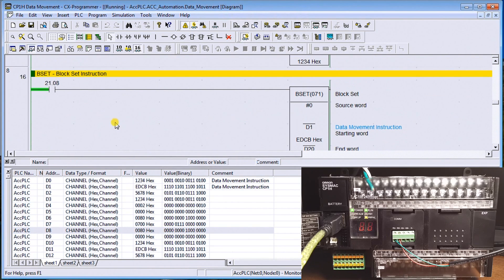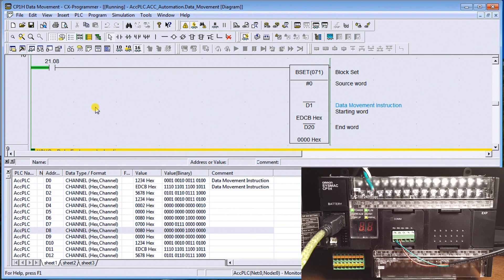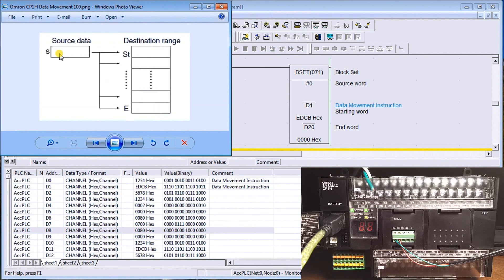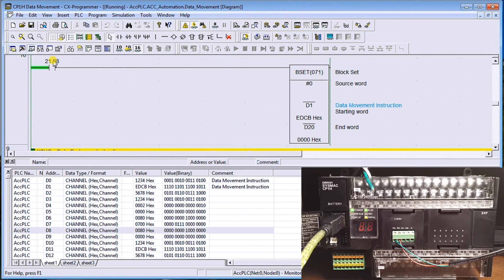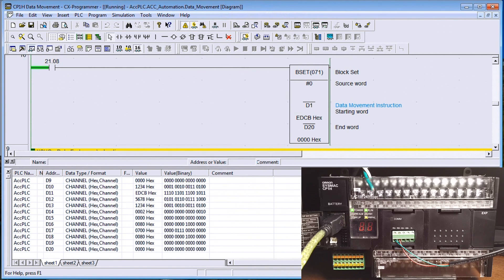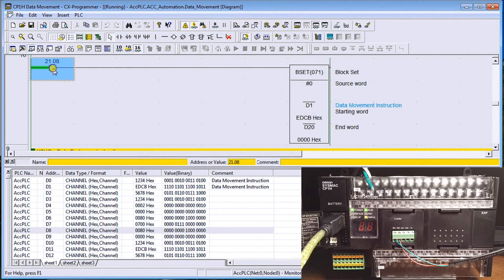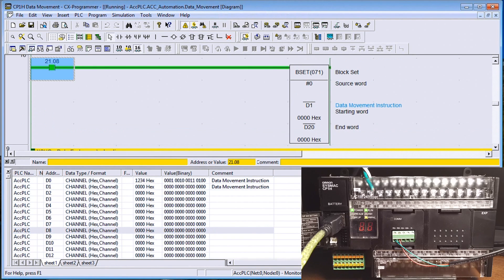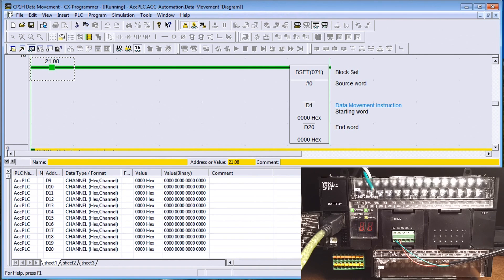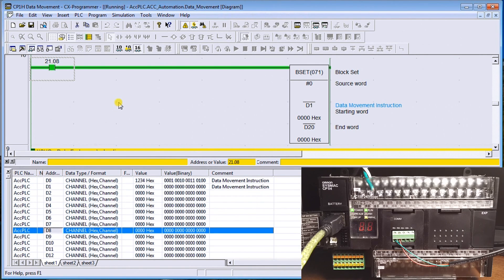Next is Block Set (BSET). It takes a value and distributes it from a starting word to an end word, filling a block of memory. In our case, it zeros from data memory one all the way to data memory twenty. Turning it on, all those registers go back to zero — except data memory zero which still contains 1234. Block Set essentially zeros out or resets those values.